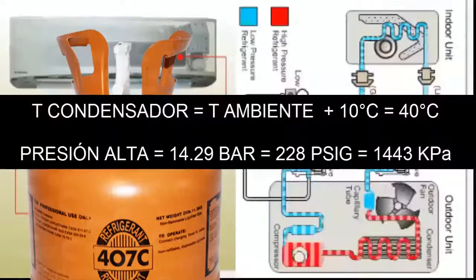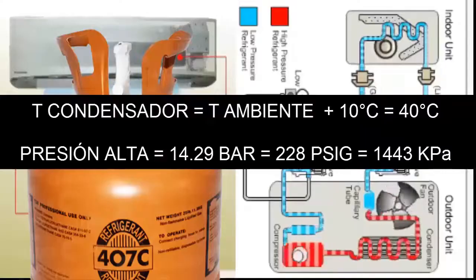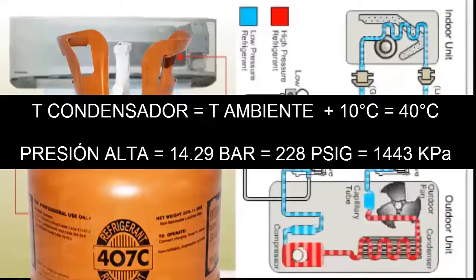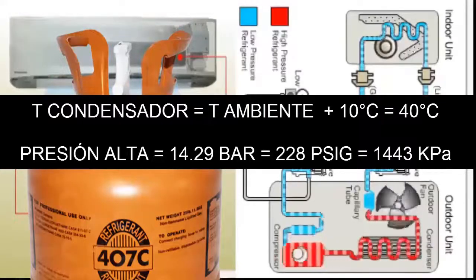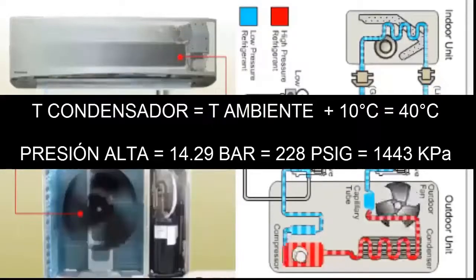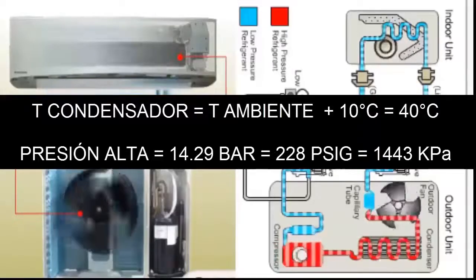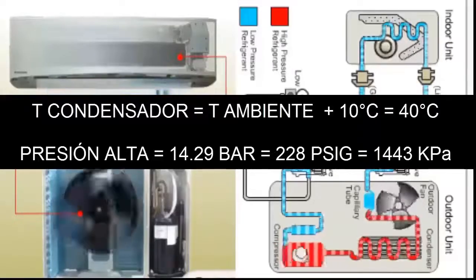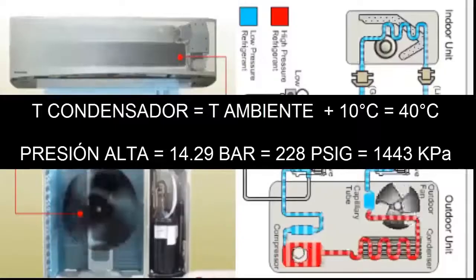For an outdoor environment temperature of 30 degrees Celsius, the condenser temperature is usually about 10 degrees Celsius above the ambient environment where the equipment is located. Thus, in the table for 40 degrees Celsius, about 104 degrees Fahrenheit, the high gauge pressure in the condenser is 14.29 bars, equivalent to 228.88 psi or 1443.29 kilopascals.